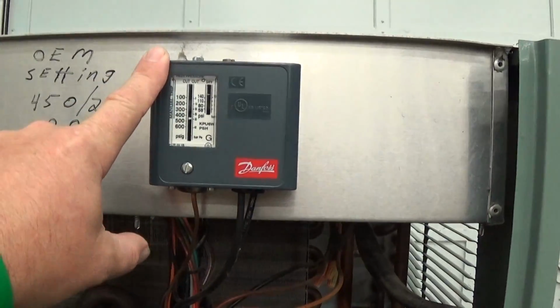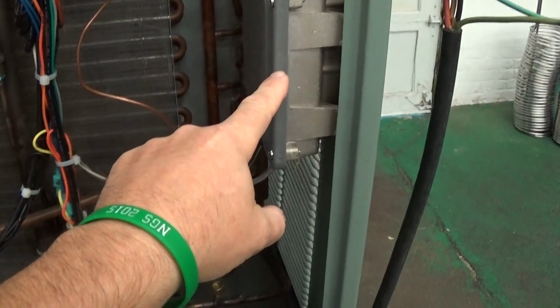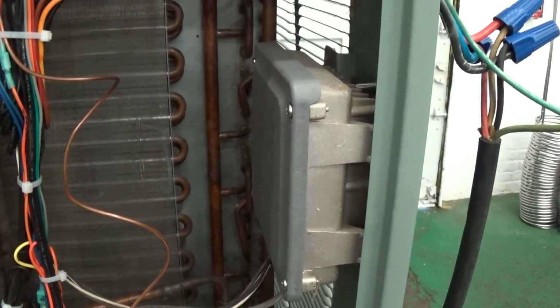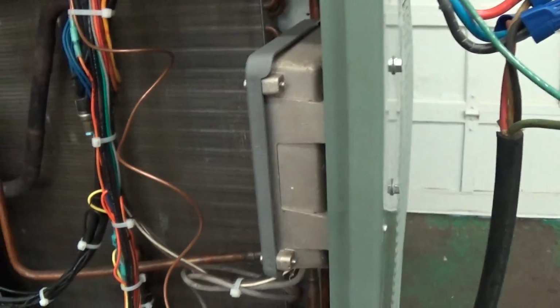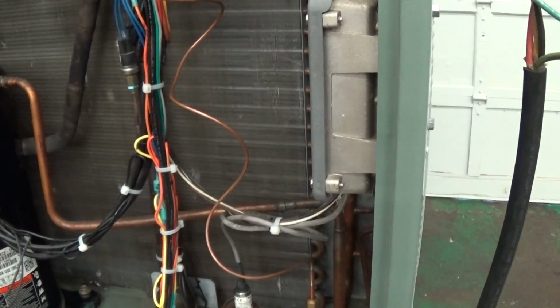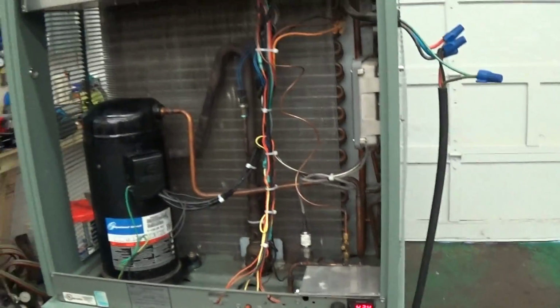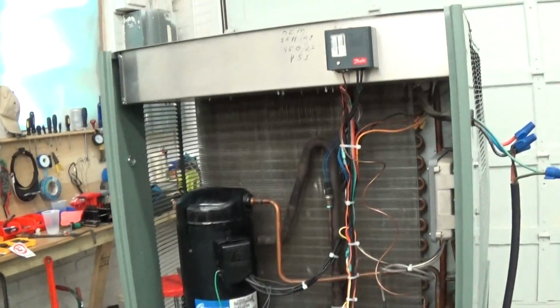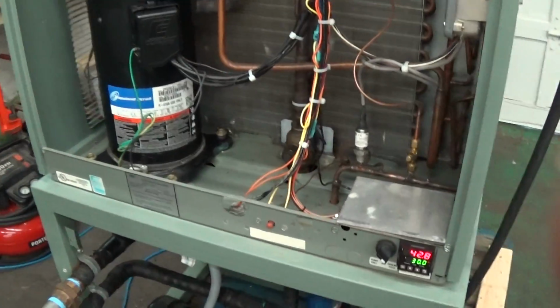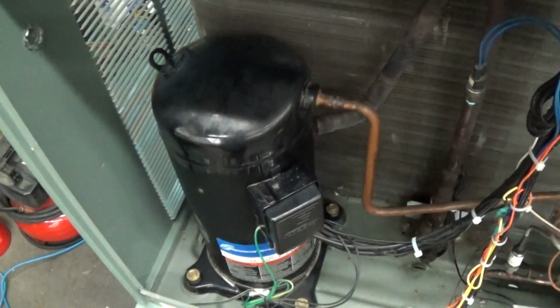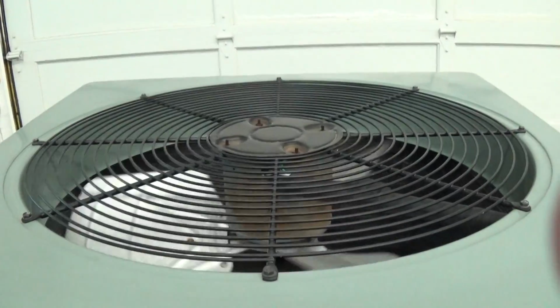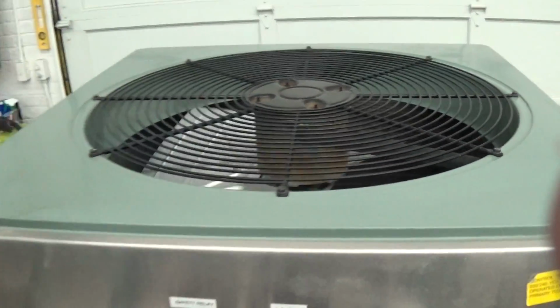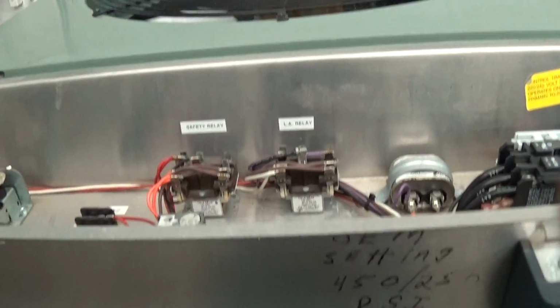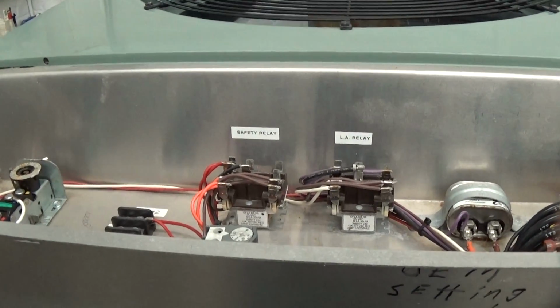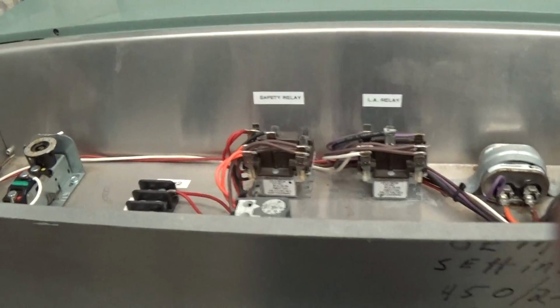This here is a high pressure switch, and that works in conjunction also with this fan switching VFD drive here to give you your low ambient feature. Unlike some other chillers, because this is designed to also be able to be outside in colder environments, the fan's not always going to be on all the time. You can see right now the compressor is running, but the fan is actually slowing down almost off. That fan will constantly be going on and off based on the high pressure readings it's seeing, and that's to help us for low ambient conditions.